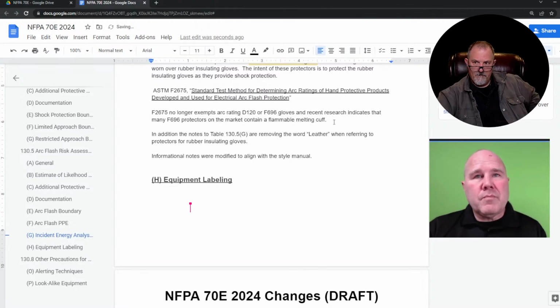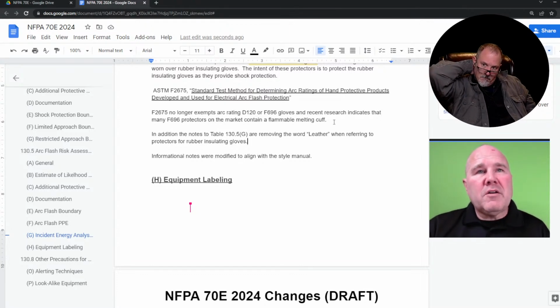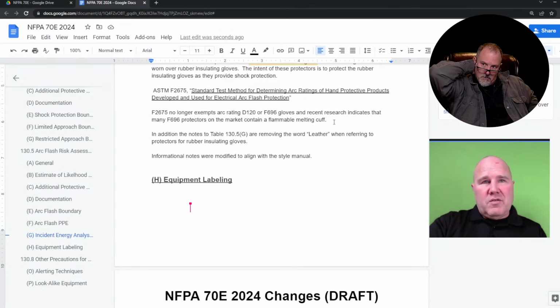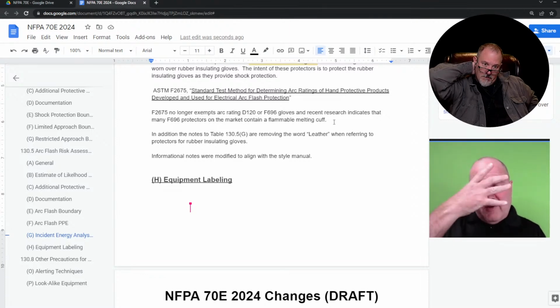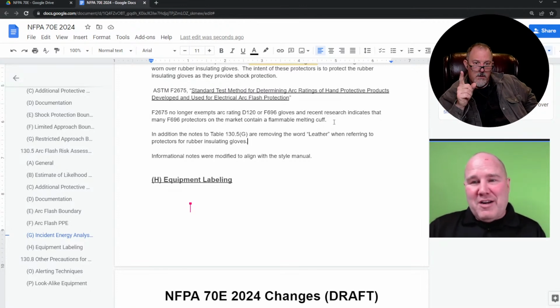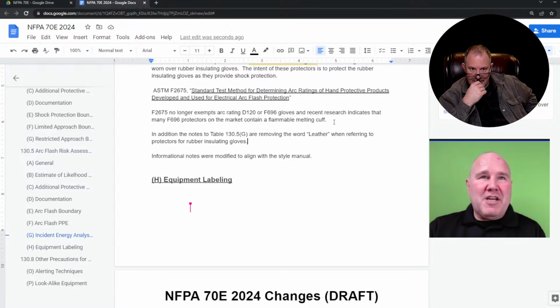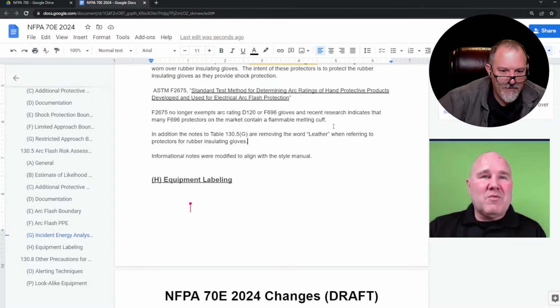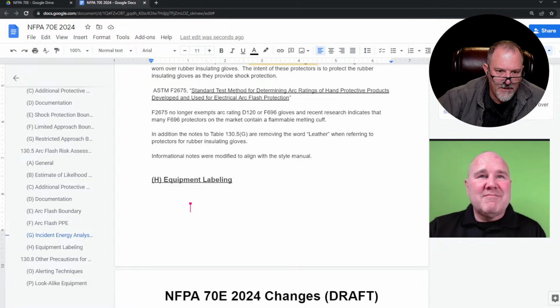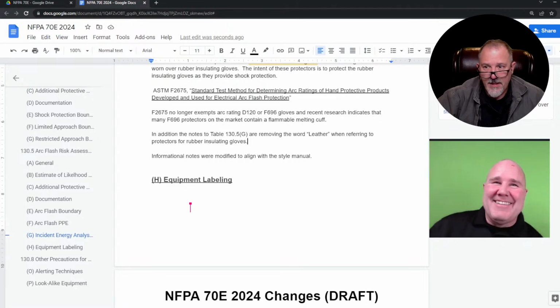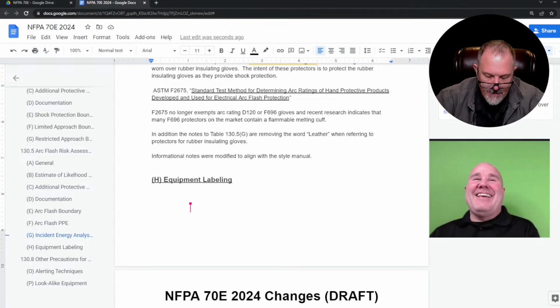You know, it's kind of interesting. You look at all of this and wonder why they don't have arc rated safety glasses or safety goggles. If you have to have a balaclava on that provides arc rating for stuff up inside your face area, why can we wear non-arc rated safety glasses? I know the face shield has to be arc rated. You look through all of table 130.5G, everything's arc rated this, arc rated that, till you get to the safety glasses. Hard hat as well. Yeah, it just says safety glasses. I wonder why. Well, they figure it'll melt around your face, they don't drip off.